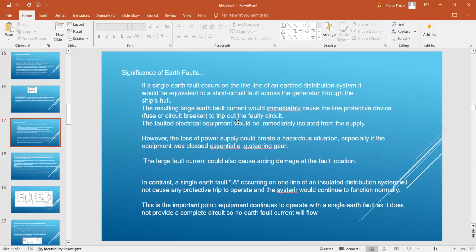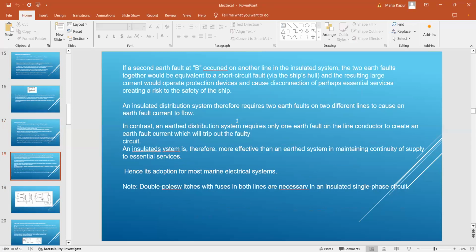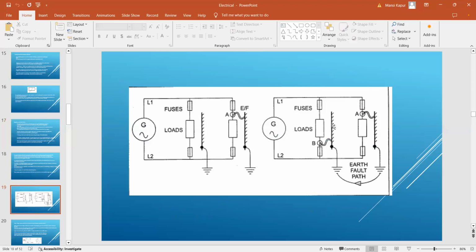In contrast, a single earth fault occurring at point A on the line of the insulated distribution system will not cause any protective device to operate, and the system would continue to function normally. This is an important point. Equipment continues to operate with a single earth fault as it does not provide a complete circuit, so no earth fault current will flow. Now, if a second earth fault occurs at B, can you see there is one more earth fault occurring at B?